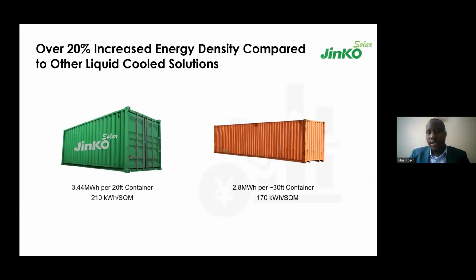One is the energy density in the containers. Looking at standard liquid cooling containers in the market, that is 20-foot containers, we're looking at close to 2.8 megawatt hours of energy storage in one container. But with the SunTera, we are looking at close to 3.44, and in the near future we may add even more to optimize the megawatt hours per container.